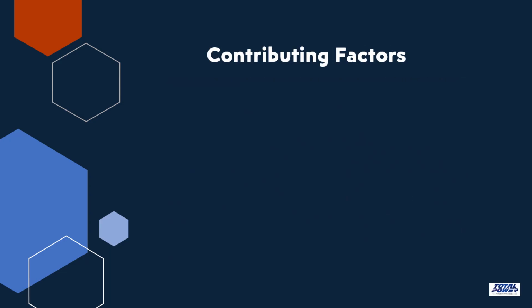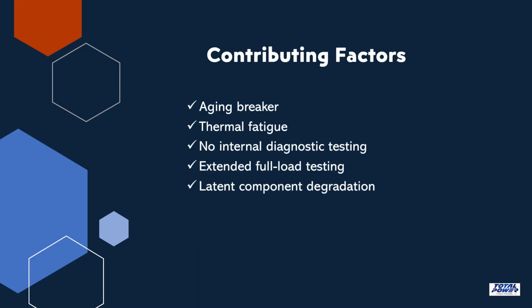Investigators also identified several contributing factors. The breaker had likely experienced years of service. Internal contacts and insulation systems degrade over time. Unfortunately, that degradation cannot be confirmed through routine visual inspections.